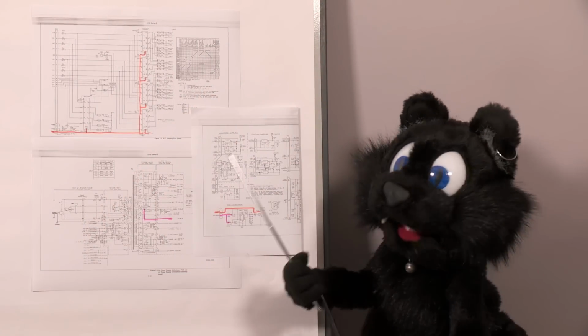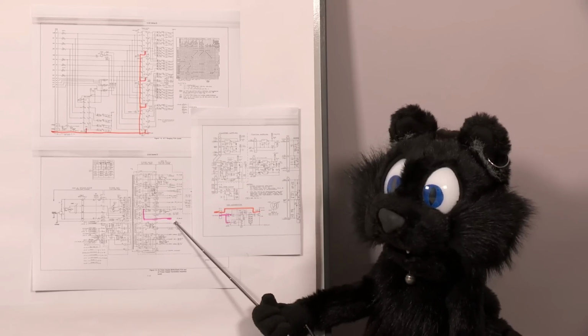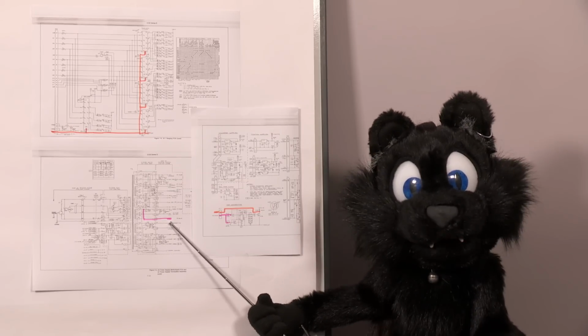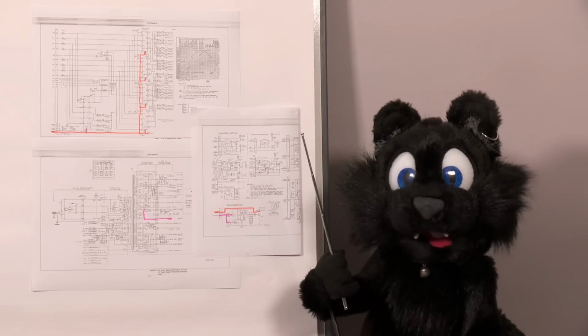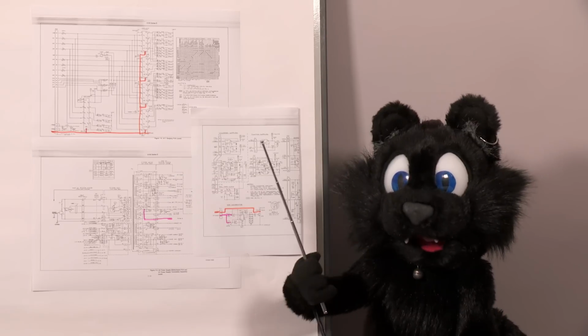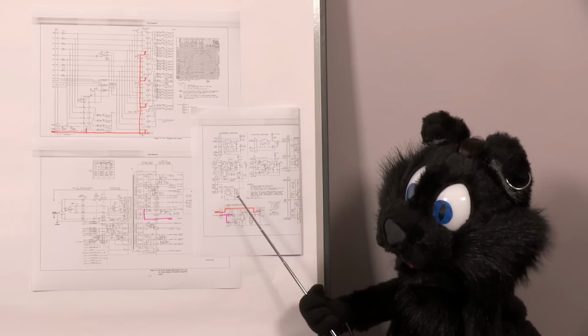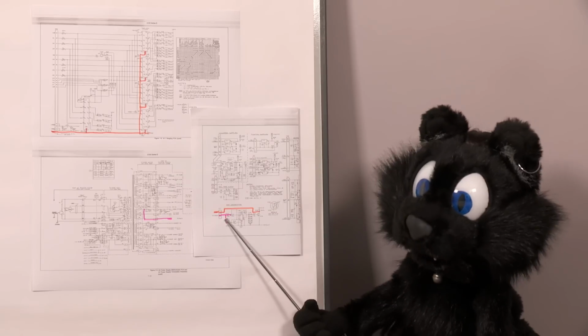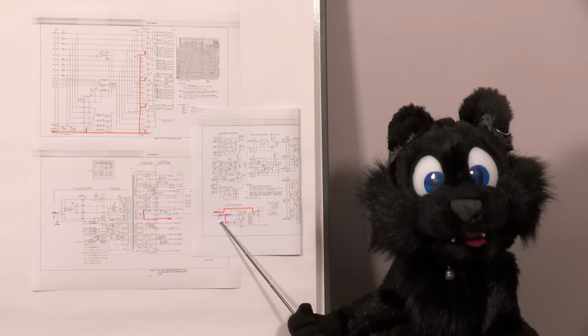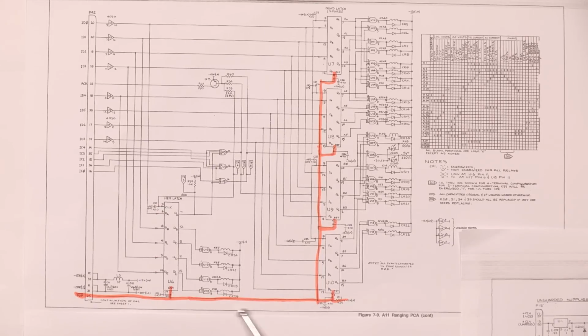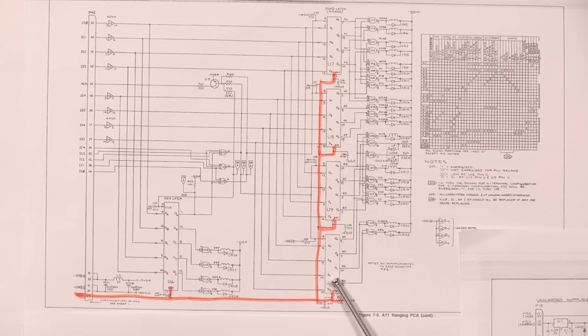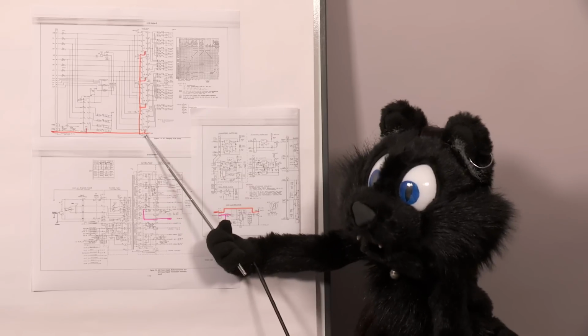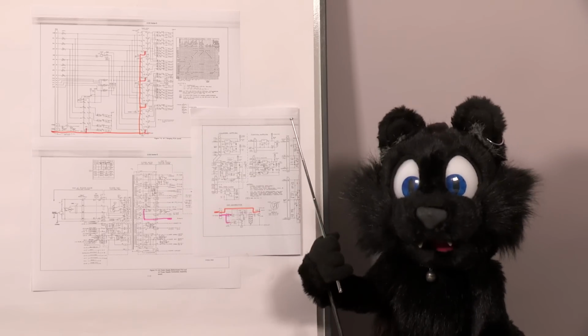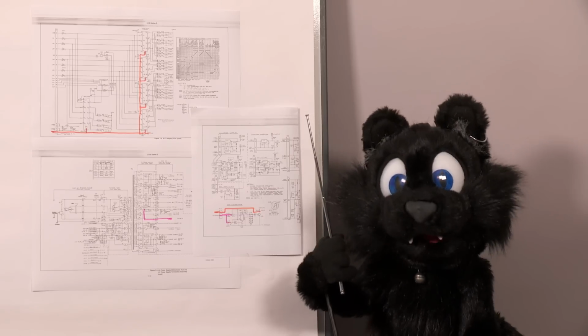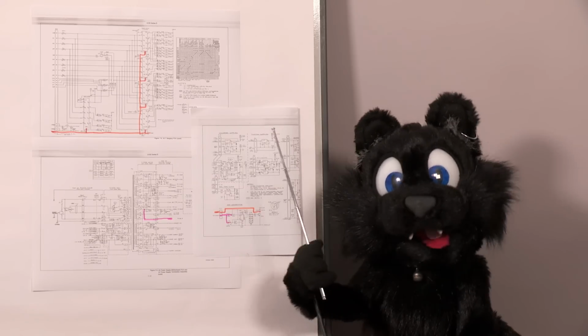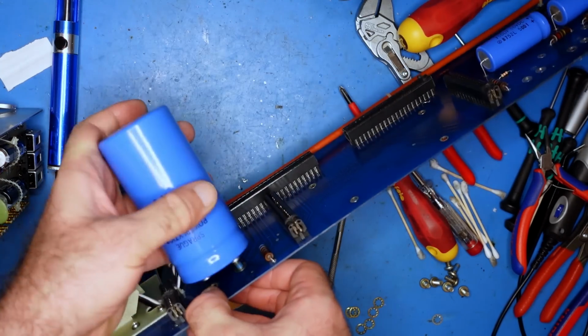I checked on the line in question. It is called POP. And yes, it surely did pop. Or rather, no longer. Well, POP is short for Power On Preset. It is essentially a reset pulse that is created on the regulator board based on this input from the transformer. Think of it as a power good style signal. It is used by all the cards in the analog section to force their relays into a safe, defined state so that during power on, even before the controller CPU has started, nothing dangerous can go to the outputs. Might this be the reason why some outputs don't work? I can hope, can't I?